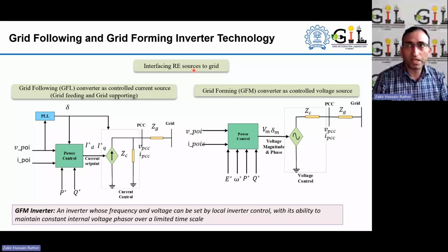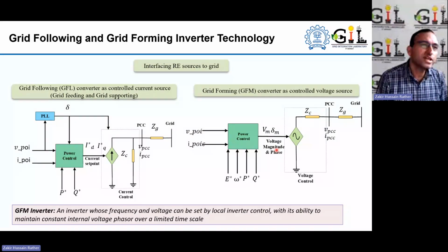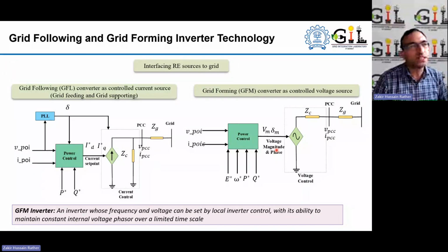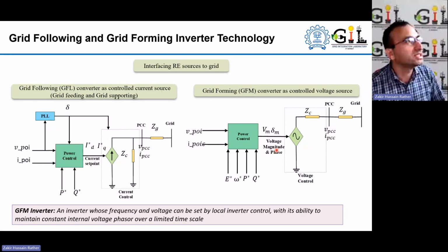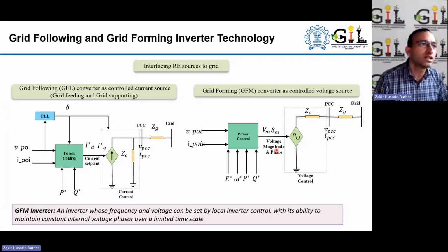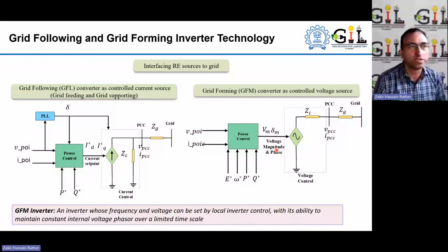Now the grid forming converter technology is primarily where we are trying to mimic the conventional generator, because if the RE technology is able to behave similar to a conventional generator, nothing better than that, because the grid operator knows very well how these conventional power plants are operated and how they help the grid. Technically speaking, these synchronous machines are beautiful grid elements, from the grid operation perspective, from the stability, because they have those inherent capabilities of grid support services. So this is somewhat in that direction in grid forming technology, where the behavior of the conventional generator is being attempted to be mimicked with this technology.